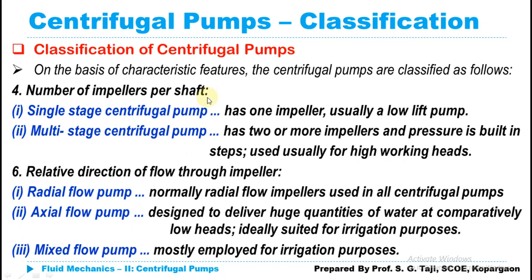The number of impellers per shaft depends on how much head you want to develop. For lower head requirements, a single-stage centrifugal pump is sufficient. For high head development, multiple impellers fixed on the same shaft are needed — known as a multi-stage centrifugal pump. According to the relative direction of flow through the impeller, a centrifugal pump can also be classified as radial flow, axial flow, or mixed flow pump. The centrifugal pump falls under the radial flow category, where discharge enters and leaves radially.